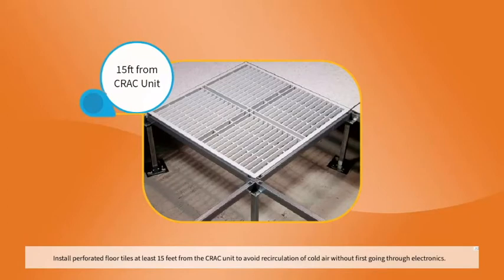Install perforated floor tiles at least 15 feet from the CRAC unit to avoid recirculation of cold air without first going through electronics.